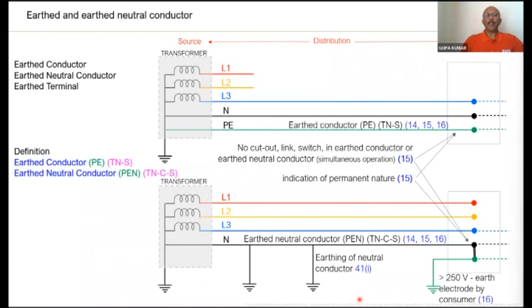Regulation 33 says insulation resistance test. Before the electricity supply company provides the electricity to a consumer premise, they are supposed to measure the insulation resistance, and regulation 31, sub-regulation 1 says periodic testing every 5 years is also necessary. So basically, for a consumer who is getting low voltage electricity from the electricity supply company, the company is supposed to ensure that all these regulations, which are mandatory safety requirements, are followed.